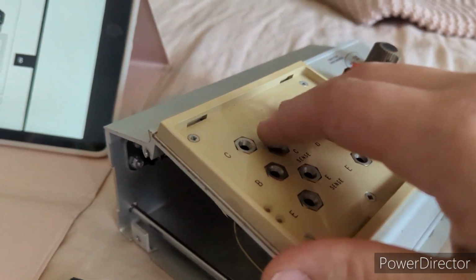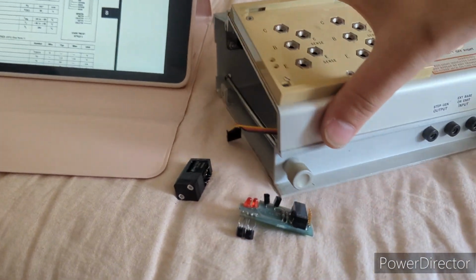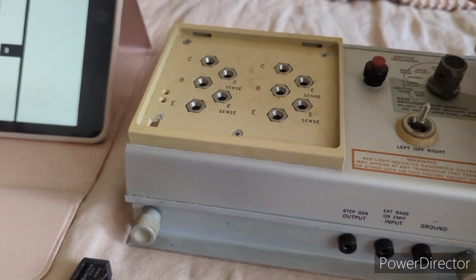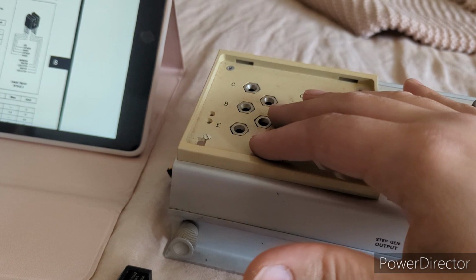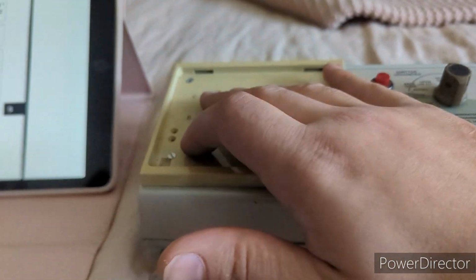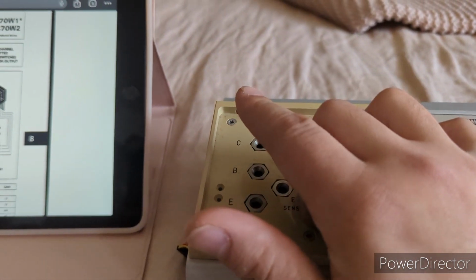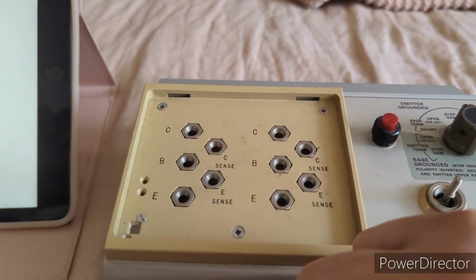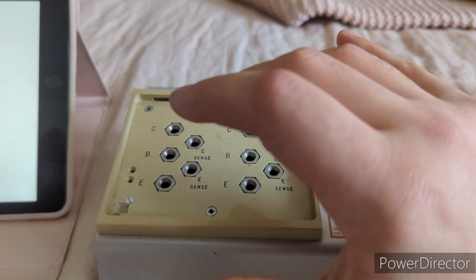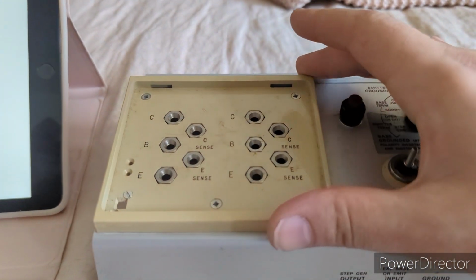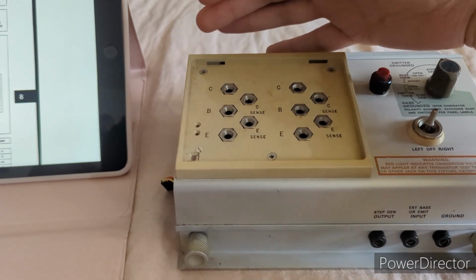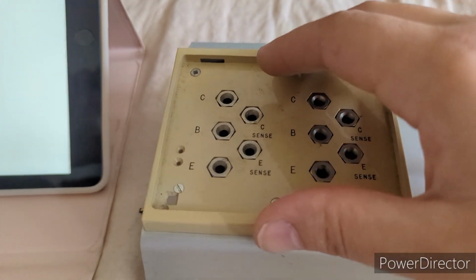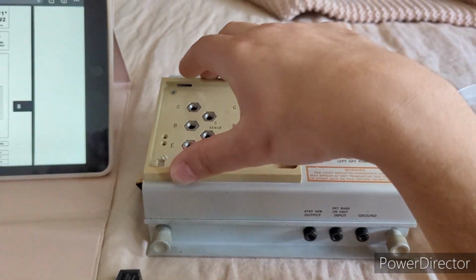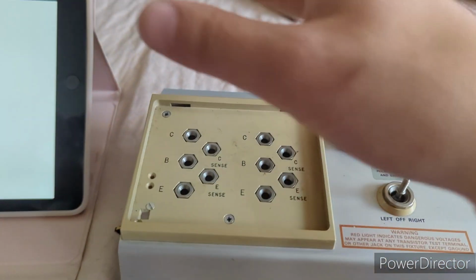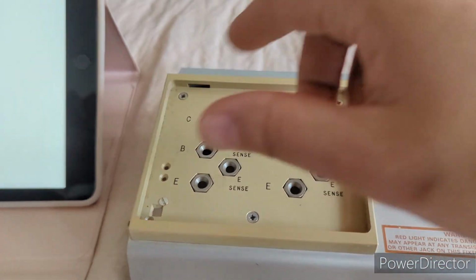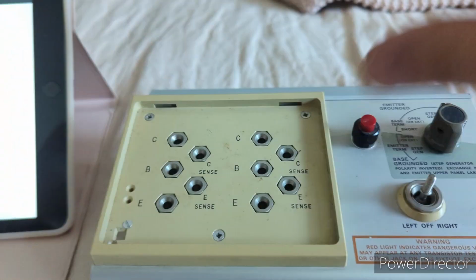But anyway, at 15 volts, the relay is automatically on applying voltage, but as soon as you get up to 75, the safety interlock kicks in and disables the voltage to the collector, and then a yellow light will come on next to that green power light. Let me first say these usually have a plastic safety box that will cover the test fixture, and until you cover this fixture with that plastic box, you won't be able to disable the safety interlock. Once you do that, the yellow light will come off, and then this red light will come on, indicating that this is live with some high voltage.